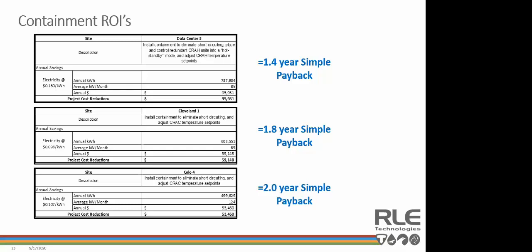Looking at the middle graph, again, a completely different data center, in a completely different part of the country. They were not placing any cooling units in standby, but just by making some cooling unit set point changes after containment was installed, we're still able to show a savings of almost 604,000 kilowatt hours a year. They were paying 9.8 cents a kilowatt hour, and that equates to just over $59,000 a year savings. In that case, that equals a 1.8-year payback.